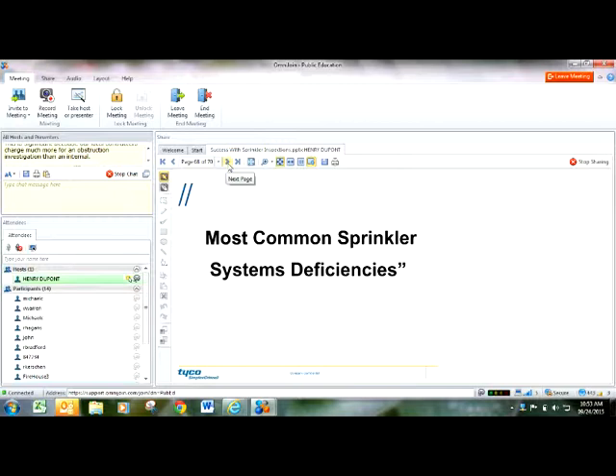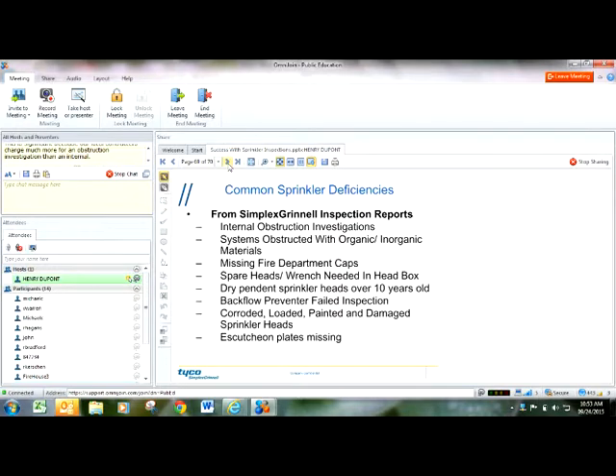Okay, the most common deficiencies that we find during our inspections: internal obstruction investigations are not carried out. It's easy to tell if these are being done or not, because if you go to the sprinkler riser, they should be tagged. It's a tag that says 5-year obstruction investigation, and there are different check marks. Did it pass this? Did it fail that? So if you question it, you should be able to walk right to the riser and see the tag. If they don't have a tag, ask them to show you their obstruction investigation results. And if they can't produce them, then they probably need to get that done.